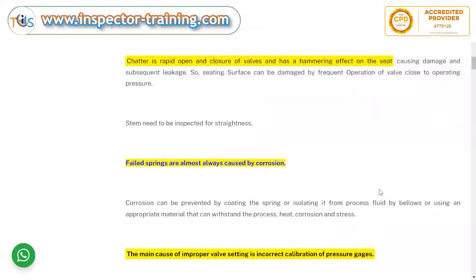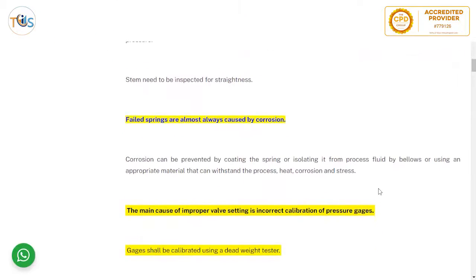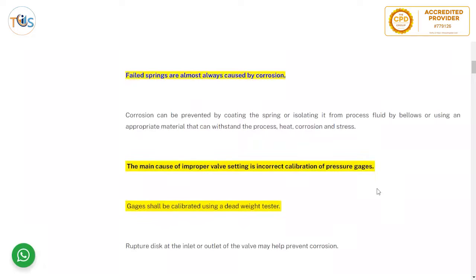Stem need to be inspected for straightness. Failed springs are almost always caused by corrosion. Corrosion can be prevented by coating the spring, isolating it from process fluid using bellows, or using an appropriate material that can withstand the process heat, corrosion, and stress.